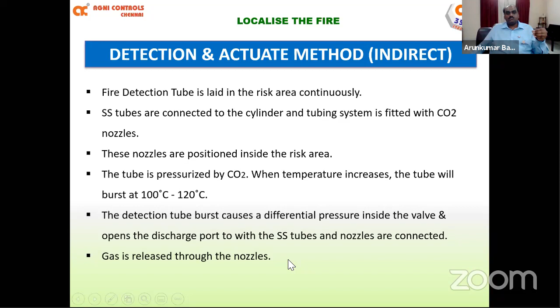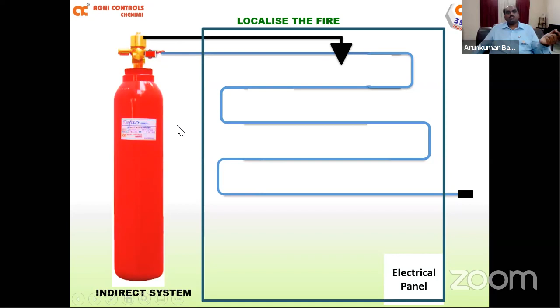This is a different kind of valve. We connect a small SS tube or small size pipe, a carbon steel pipe, which is connected here via a nozzle. I'm going to energize the system again. If you see, the ball valve is turning, so the entire detection tube is now going to be pressurized with 20 bar carbon dioxide, and the system is ready for operation.